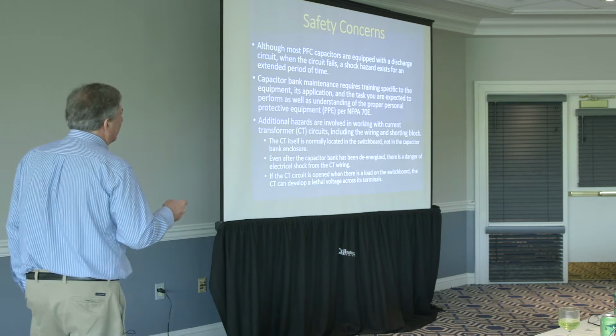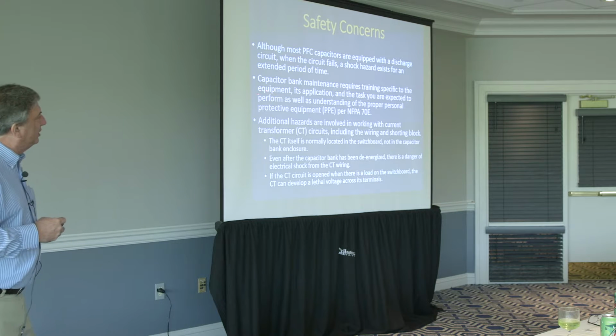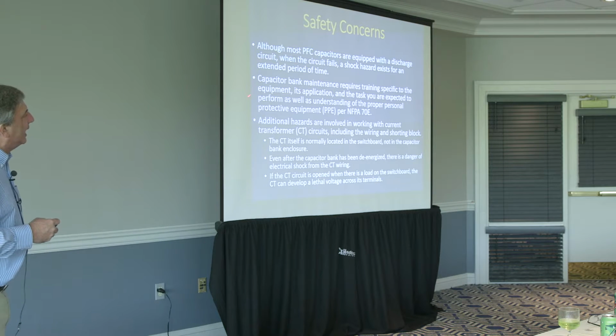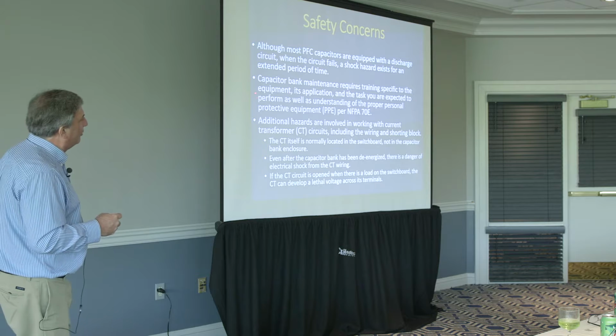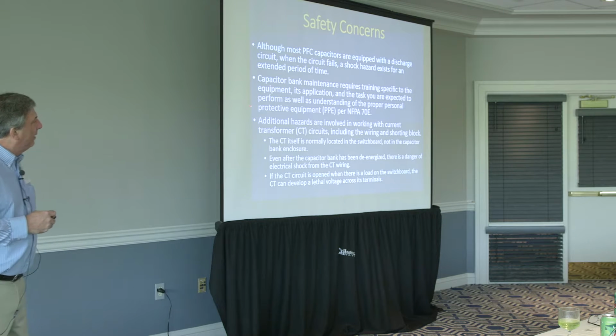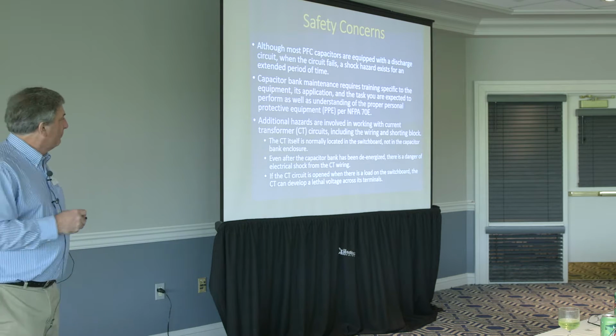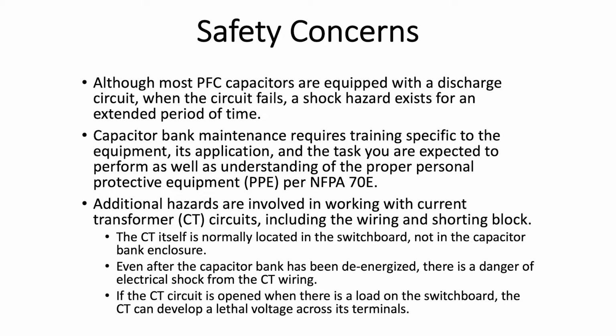So capacitor bank maintenance requires training specific to the equipment, its application, and the task you're expected to perform, as well as understanding proper PPE. Additional hazards are involved in working with current transformer circuits, including the wiring and shorting block for the cap bank. The CT itself is normally located in the switchboard, not in the cap bank enclosure.